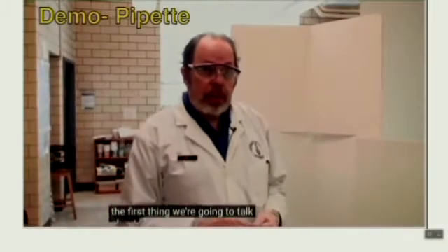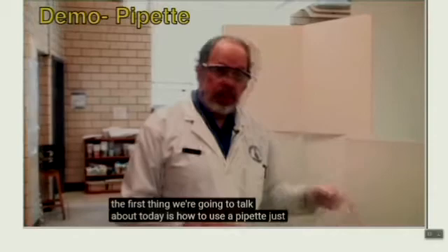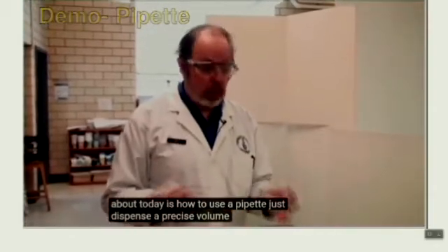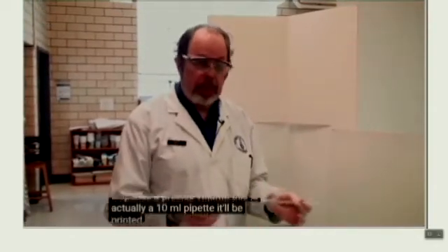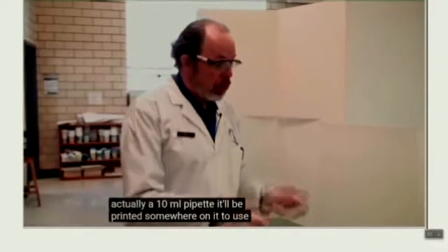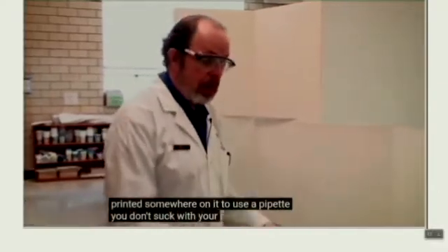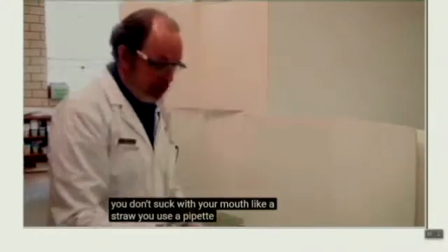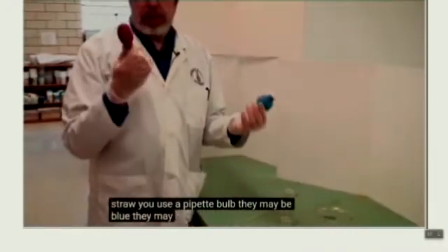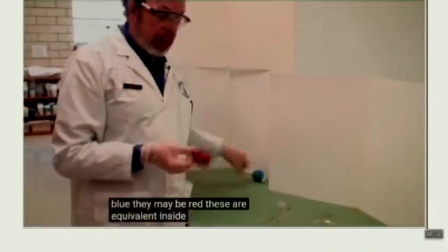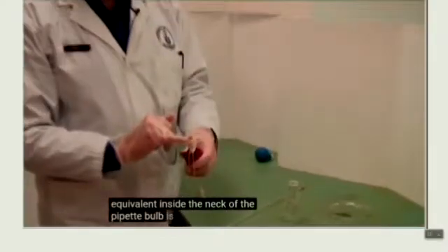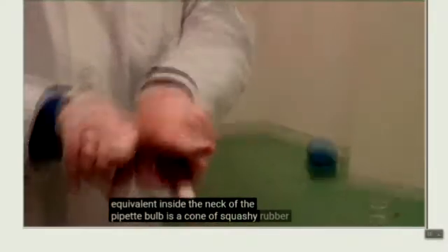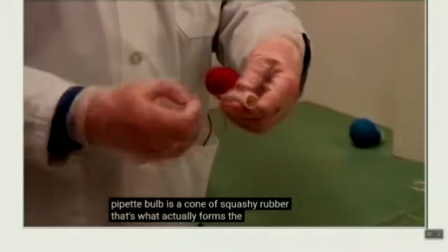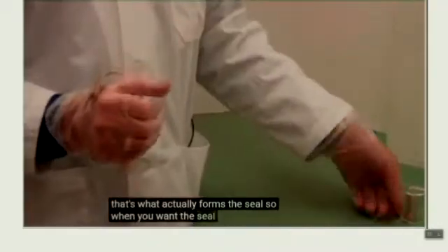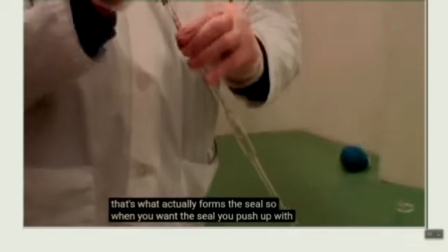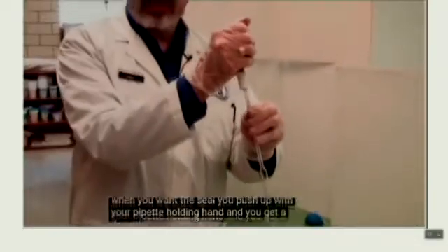The first thing we're going to talk about today is how to use a pipette to dispense a precise volume. This is actually a 10 ml pipette. It'll be printed somewhere on it. To use a pipette, you don't suck with your mouth like a straw. You use a pipette bulb. They may be blue, they may be red. These are equivalent. Inside the neck of the pipette bulb is a cone of squashy rubber. That's what actually forms the seal. So when you want the seal, you push up with your pipette holding hand and you get a decent seal here.